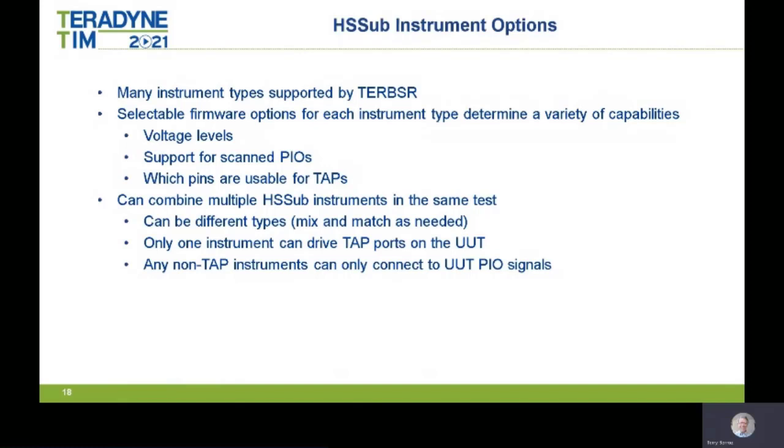You can combine multiple different HSSub instruments in the same test. You can mix and match as needed. Note that only one instrument can drive tap ports on the UUT. All additional instruments in the test can only connect to UUT PIO signals.